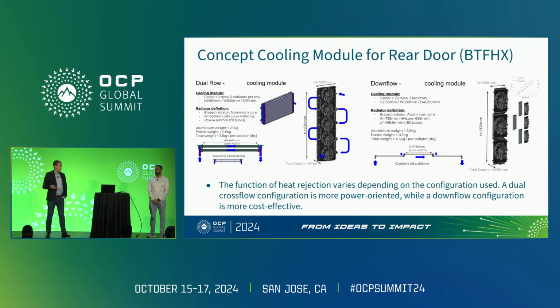That means we are able, as shown by Mohamad through the table, to divide by 2 the internal volume used for the coolant, and to divide by 2 the weight of the exchanger. At the end, through the air pressure drop reduction, we also have some electrical consumption savings. Concerning the CO2 footprint, it is very interesting.